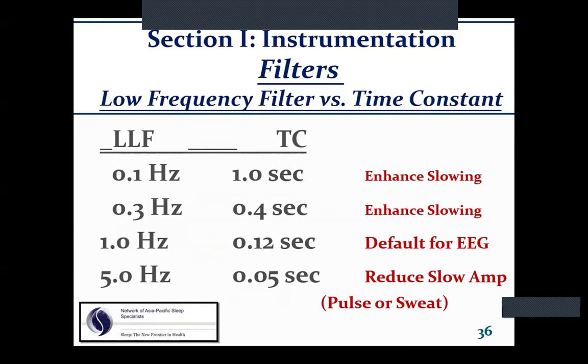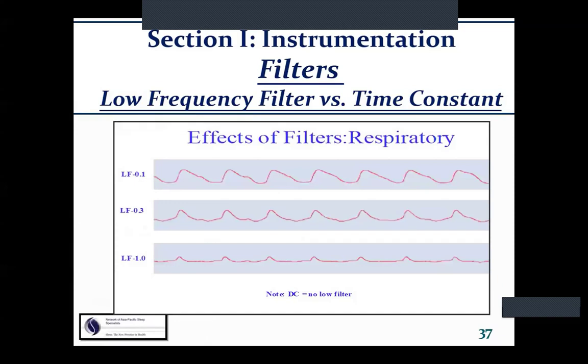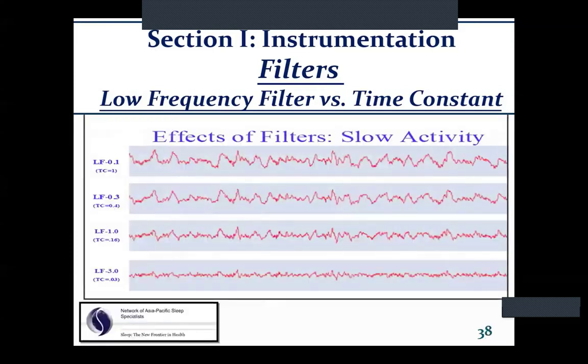Then if we had problems with pulse or sweat, you're going to use a 5 Hertz low filter and then a 0.05 second time constant. So let's see how that might affect some of our channels. With the low filter, if I'm at 0.1, we get beautiful respirations. If we turn it up to 1, you're not going to get any readable, reliable data. So the effect of the low filter on slow activity, we see up here, we're at a low filter of 0.1 or a time constant of 1. We get beautiful data, easy to interpret, easy to stage.